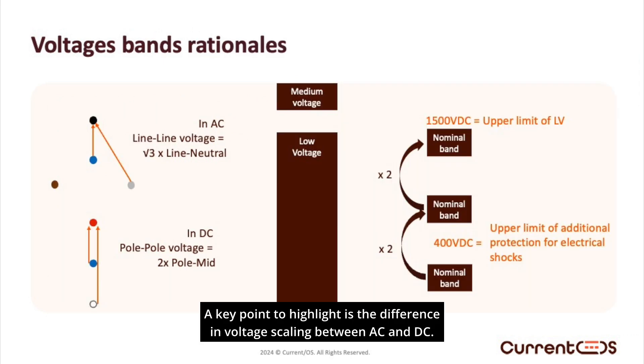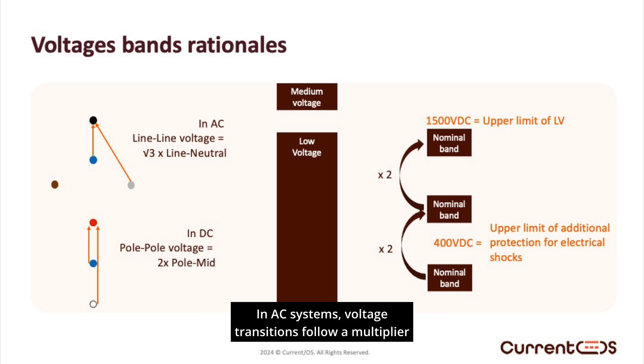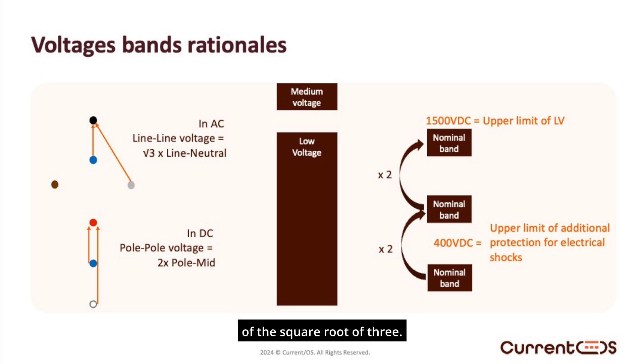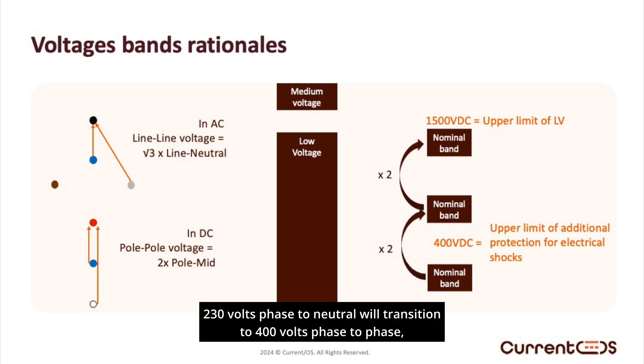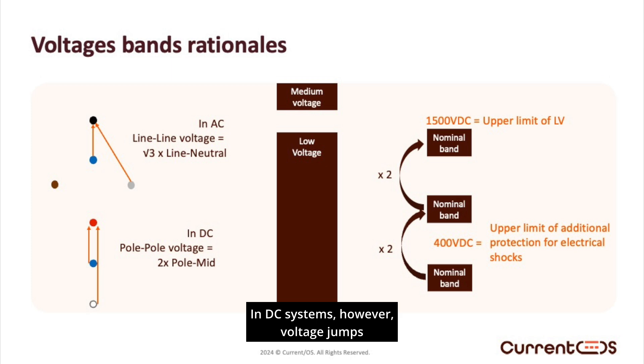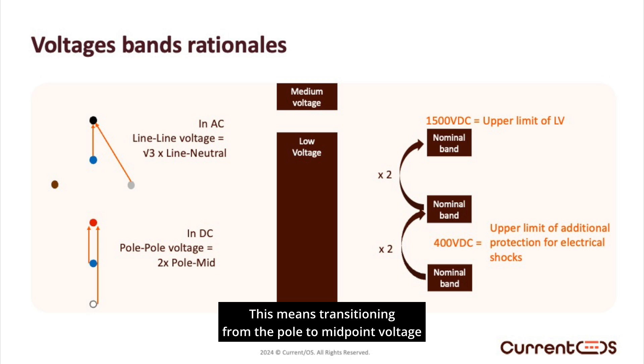A key point to highlight is the difference in voltage scaling between AC and DC. In AC systems, voltage transitions follow a multiplier of the square root of 3. For example, 230 volts phase-to-neutral will transition to 400 volts phase-to-phase, and 400 volts will transition to 690 volts in certain applications. In DC systems, however, voltage jumps are based on a factor of 2, meaning transitioning from pole-to-midpoint voltage to pole-to-pole voltage is achieved by doubling the value.